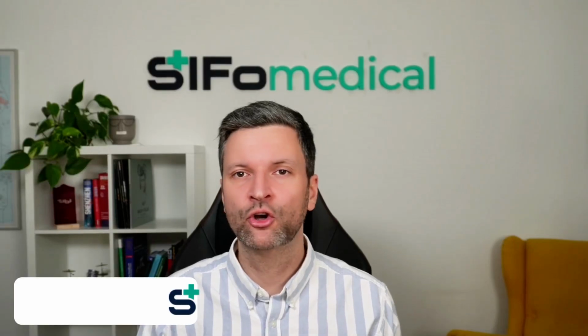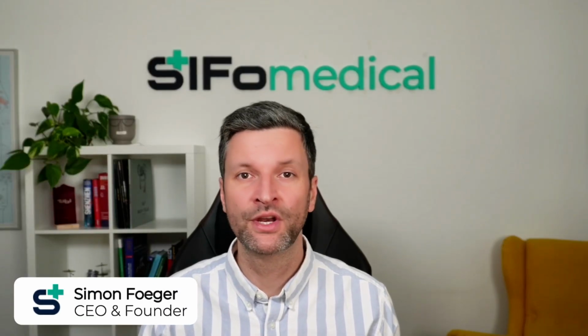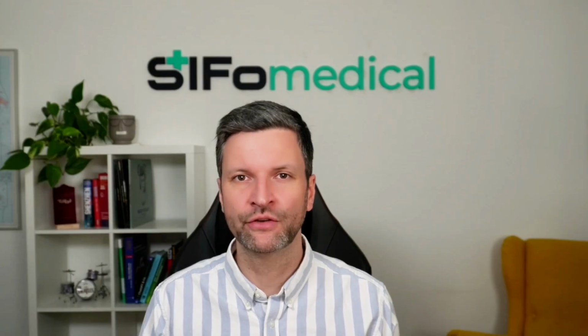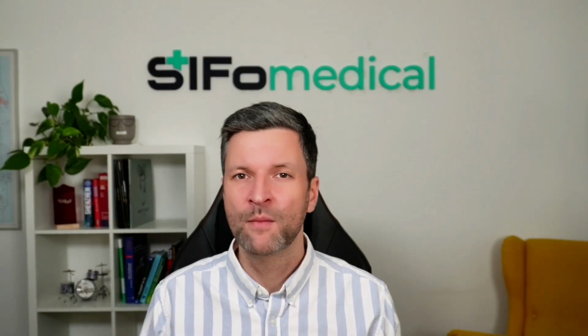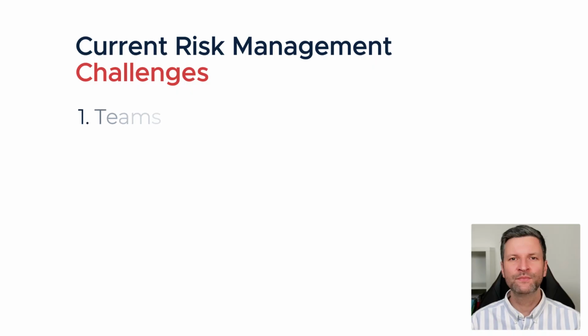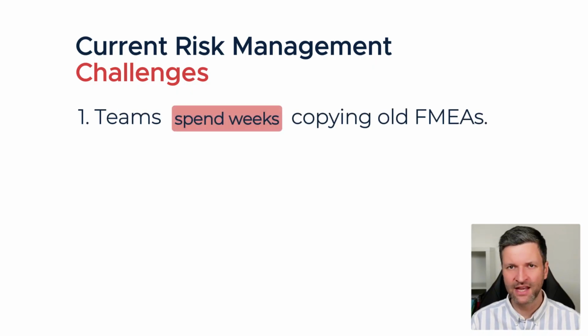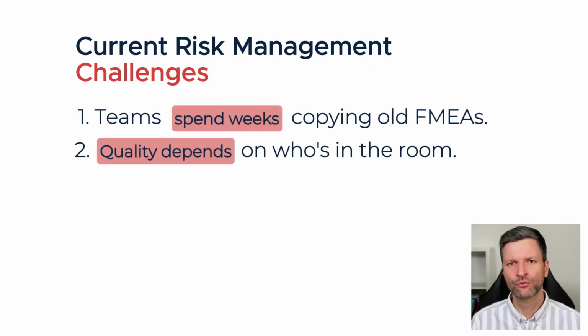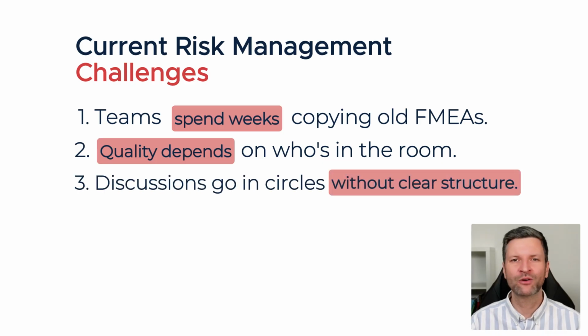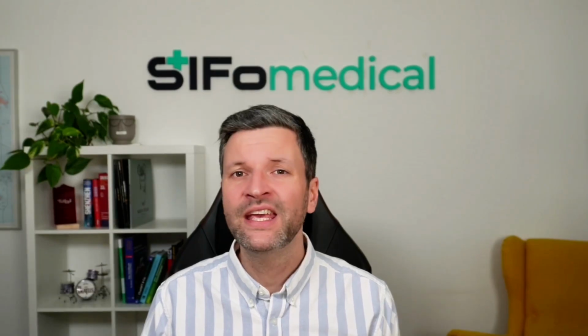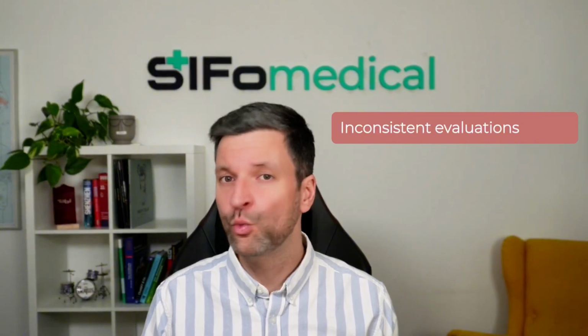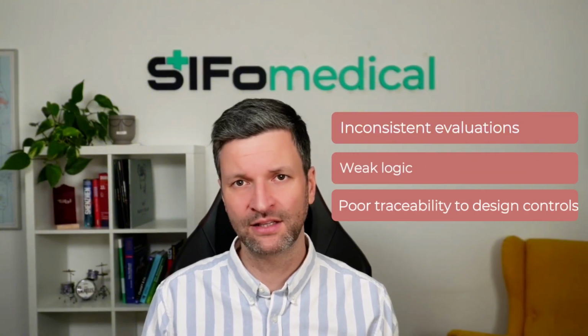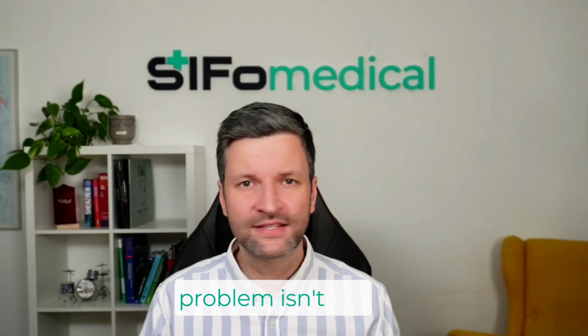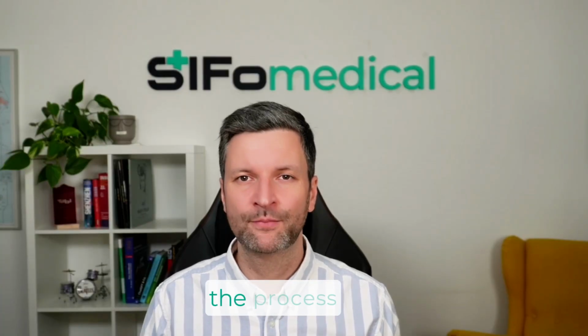Risk analysis, according to ISO 14971, is supposed to be the foundation of safe medical device development. But here's what actually happens. Teams spend weeks copying old FMEAs, quality depends on who's in the room, discussions go in circles without clear structure. And in audits, inconsistent evaluations, weak logic, poor traceability to design controls. The problem isn't the standard. The problem is the process.